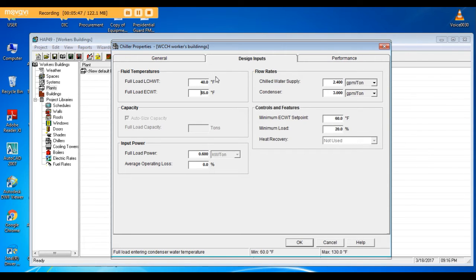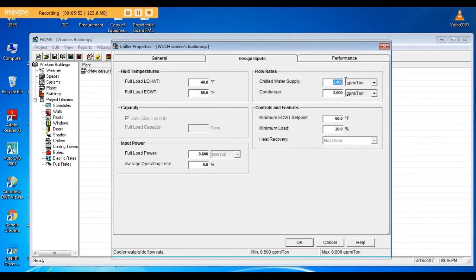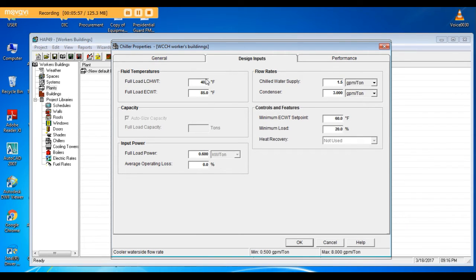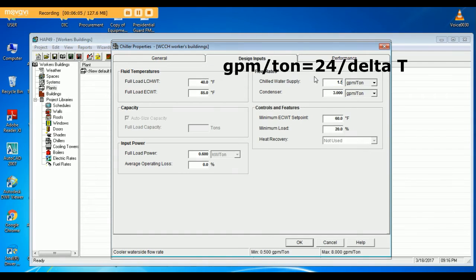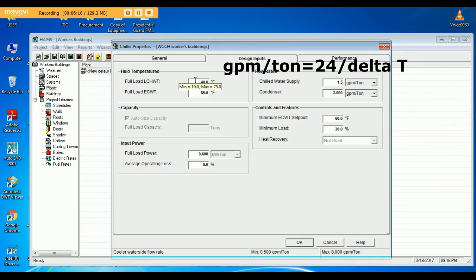Delta T 16 means the chilled water supply is 1.5 GPM per ton. In case Delta T is 10, chilled water supply will be 2.4 GPM per ton. You can follow this formula to know how much GPM per ton depending on the Delta T.